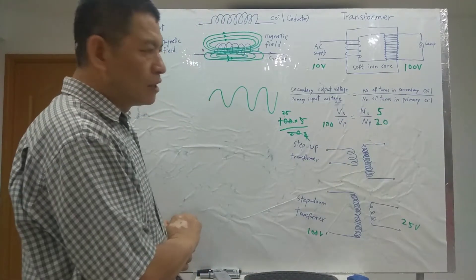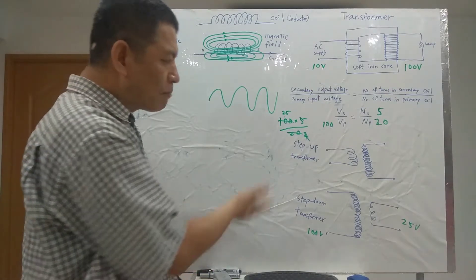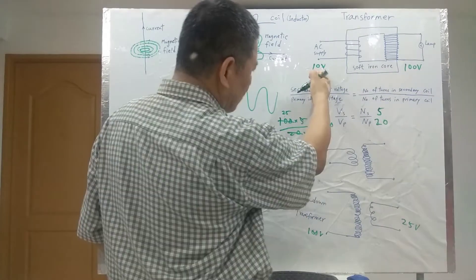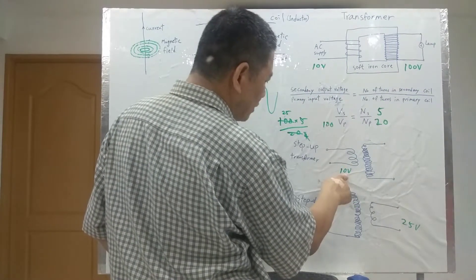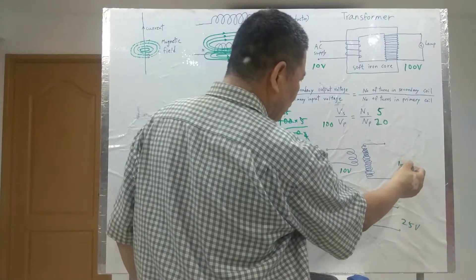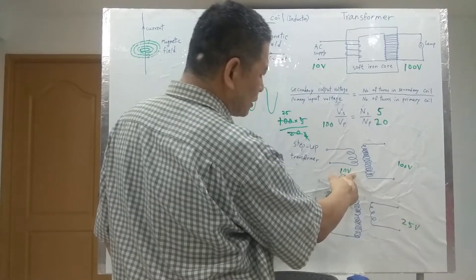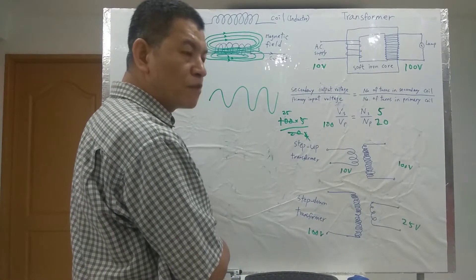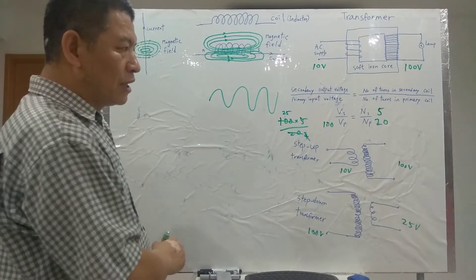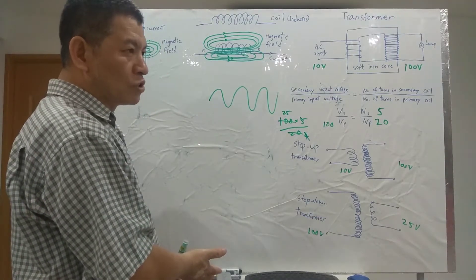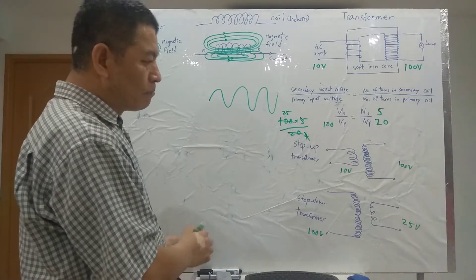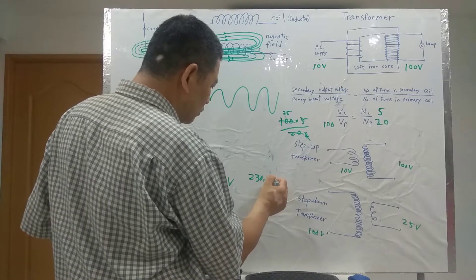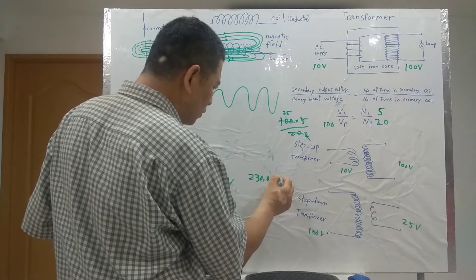This is the theory of the transformer — it can step up or step down. For the step-up transformer, the primary input is 10V and the secondary output is 100V, so the ratio is 1 to 10. The step-up transformer has practical functions, like a power station stepping up its voltage to very high power — from maybe 230V, stepping up to 230,000V.